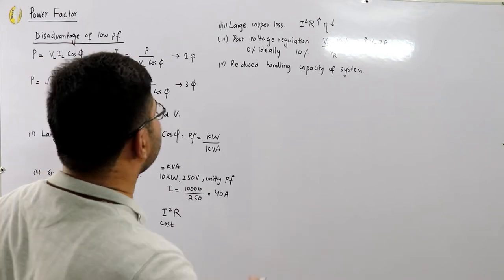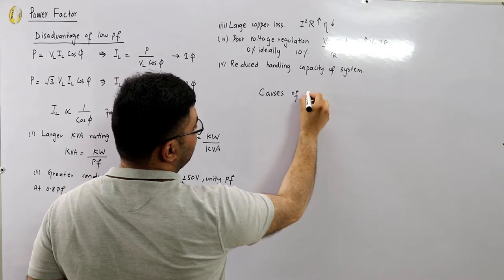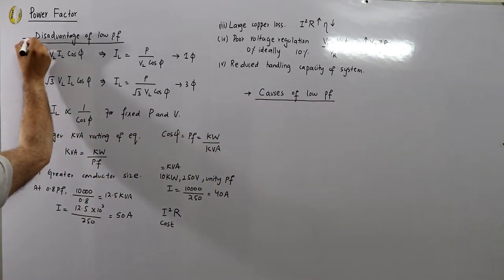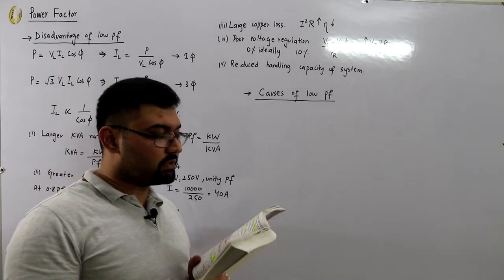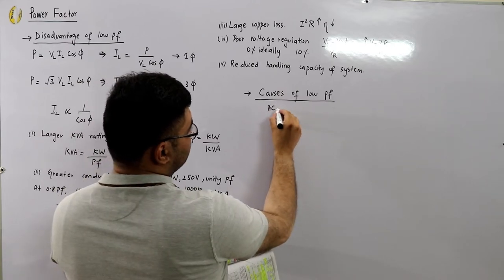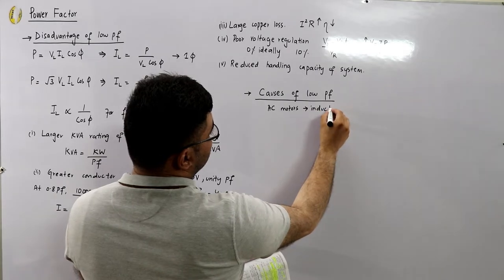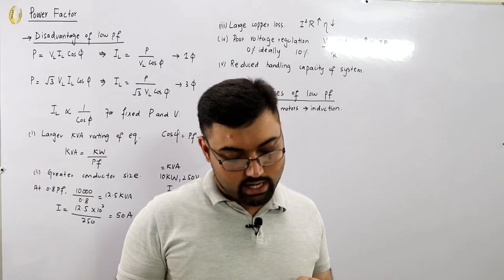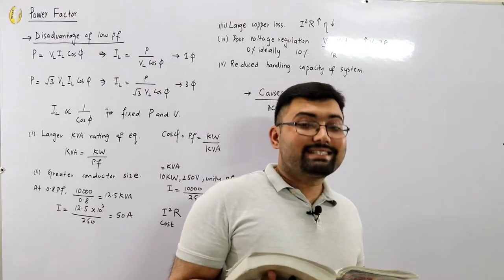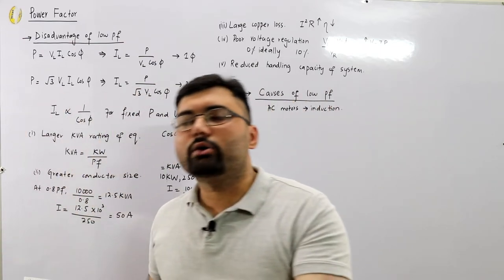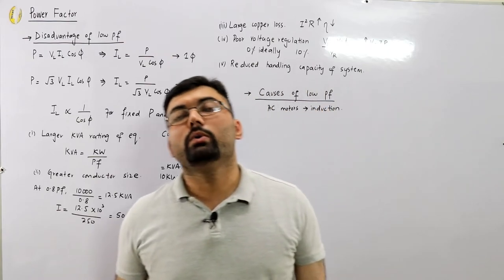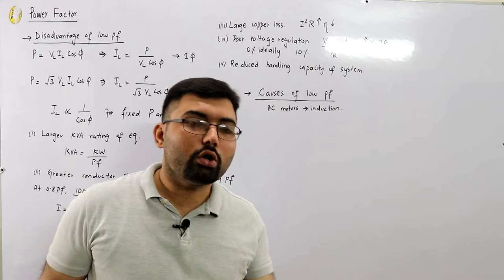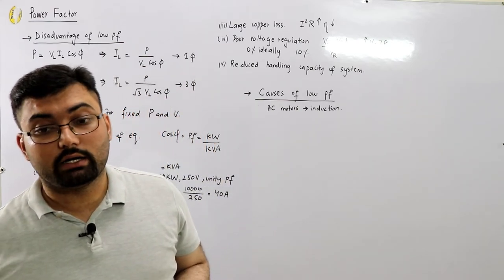Moving to the causes of low power factor: the first cause is that most AC motors are of the induction type. Three-phase and single-phase induction motors have very low lagging power factors. At no load they can fall as low as 0.2 to 0.3 power factor lagging, whereas at full load the power factor rises to around 0.7 to 0.8.